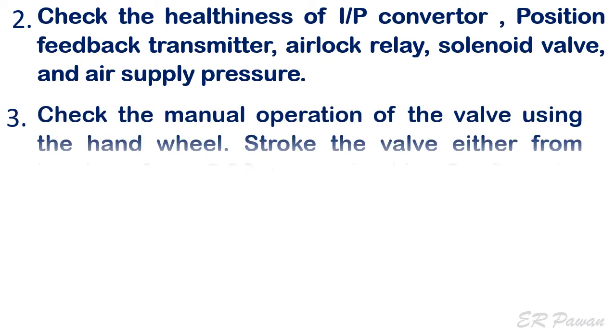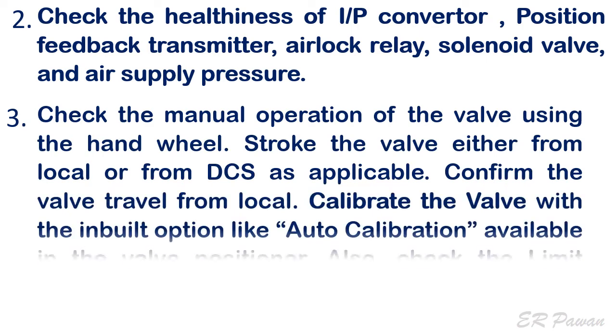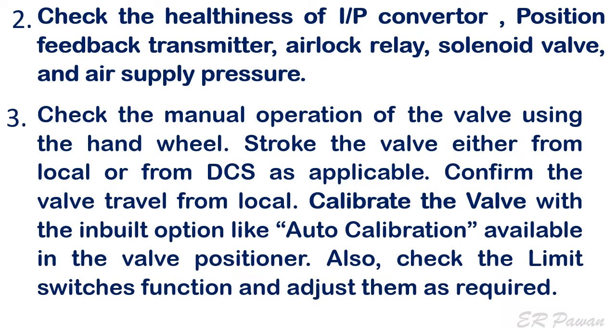Step 3: Check the manual operation of the valve using the hand wheel. Step 4: Stroke the valve either from local or from DCS as applicable. Step 5: Confirm the valve travel from local.